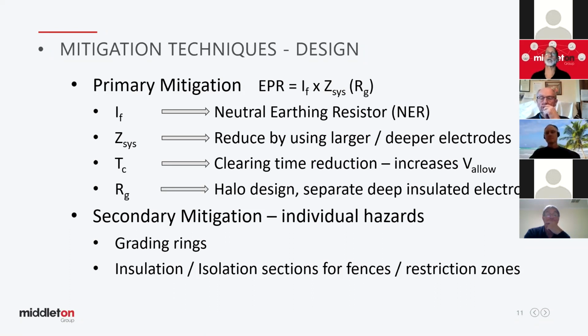In some special cases, generally we try and get the RG of the grid low. If we can get it low enough, EPR is low enough, and touch voltages are low enough to comply. However, that's not always achievable. Quite often, not particularly often, but in special cases we can do what we call a halo design and actually increase the resistance of the grid purposely. When you look at your fault calculations and take into consideration the resistance of the grid, rather than just zero as a bolted fault, it'll reduce your current, which reduces your voltage, which reduces your touch voltages.